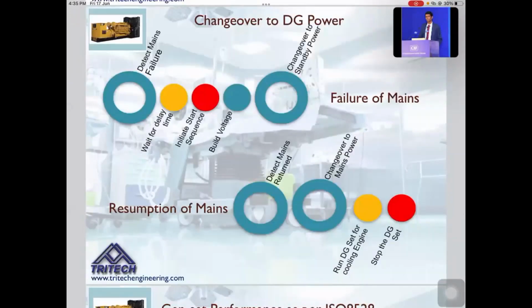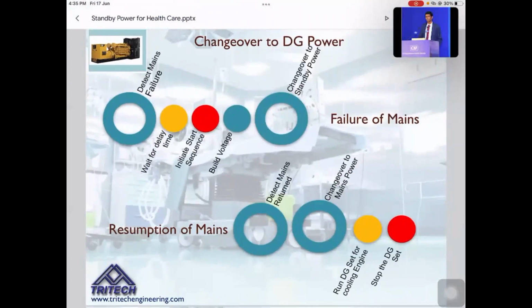And this is another slide which explains the mains failure and the time delay for start. When the mains fail, you need to ensure that the failure is actually happening, which means that for a small surge, the generator should not start. Then it should start the generator sequence, which will be starting the engine and building up the speed. Then once the voltage is built up, only then do you change over to the generator power. Similarly, the same sequence is followed in return, but what is important about switching off is that you cannot switch off the generators just like that. You have to ensure that the generator runs for 2 to 3 minutes, so that the cooling systems are distributed properly, and for most water-cooled engines, the water needs to be circulated and cool down properly. Only then should you shut down.